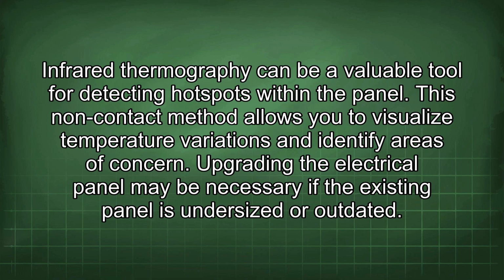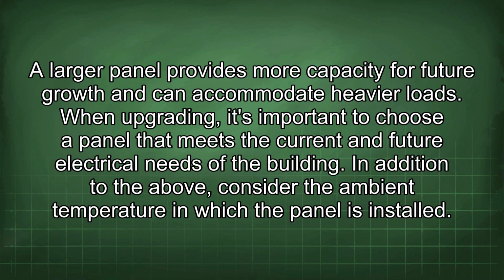Upgrading the electrical panel may be necessary if the existing panel is undersized or outdated. A larger panel provides more capacity for future growth and can accommodate heavier loads. When upgrading, it's important to choose a panel that meets the current and future electrical needs of the building.